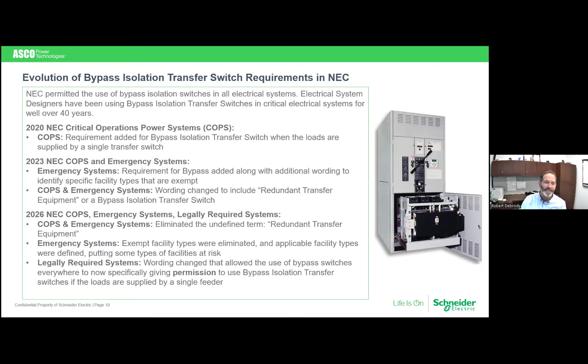And now in this newest version of the code, they got rid of the term redundant transfer equipment because it wasn't defined anywhere. Understandably, it just caused more confusion than it was worth, so they got rid of it altogether. They changed in emergency systems what types of facilities are exempt, which we'll talk about later. And in legally required systems, they said, you know what, if it was so important for COPS and it was so important for emergency systems, maybe it's something we should put in here for legally required standby systems. And then they said, well, we don't want to mandate it. Let's just tell them that we're giving them permission to use a bypass isolation transfer switch, which is kind of funny. So we'll talk a little bit about that in the coming slides. But that just kind of gives you a feel for how things may evolve here with the NEC.